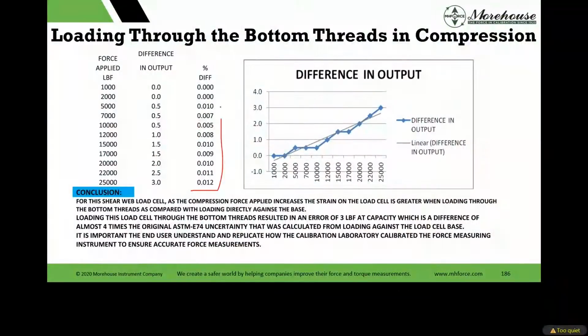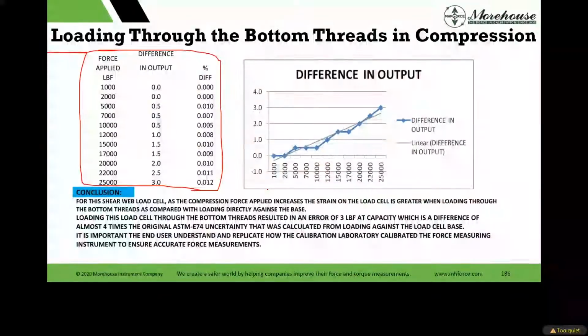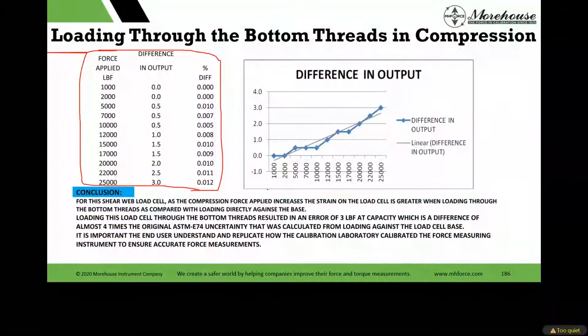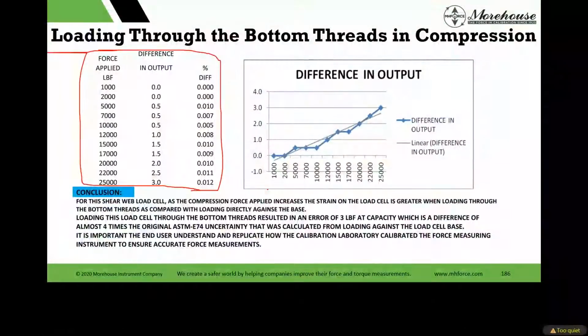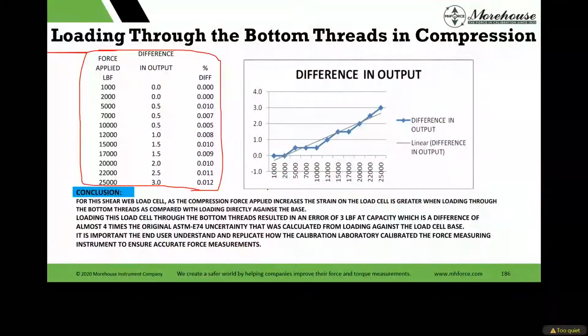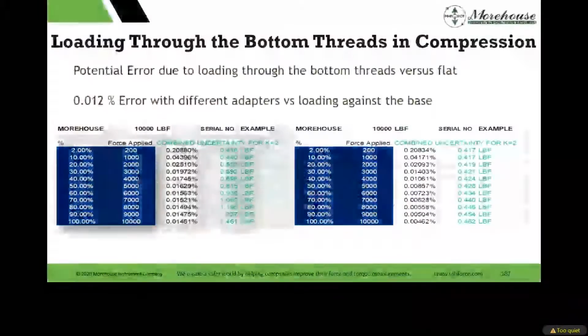This one, luckily, I had the instrument that I was testing with for this case that you got the slide for, 25,000 pound load cell. The difference was 3, that's 0.012%. If my resolution were better than 0.5, maybe that was 2.9, maybe it was 2.8. Typically, we see about 0.1. That's what happens. You can kind of account for it. I don't know if you want to correct for it because it's a little variable. The easiest thing is just to ask the customer and try to replicate the use. As I said, most people will load it flat.